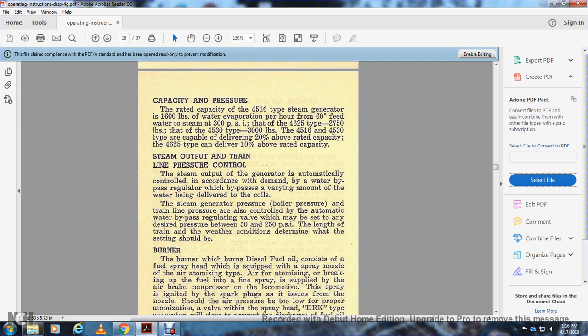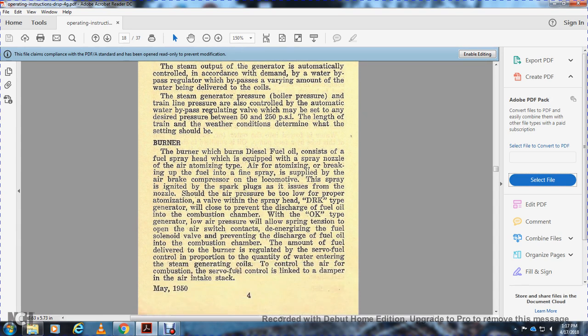Steam output and train line pressure control. The steam output of the generator is automatically controlled in accordance with the demand by the water bypass regulating valve, which varies the amount of water being delivered into the coils. Steam generator pressure, boiler pressure, and train line pressures are controlled with the automatic water bypass regulating valve, which may be set in any desired position between 50 and 250 psi, depending on the length of the train. Weather conditions determine what the setting should be.